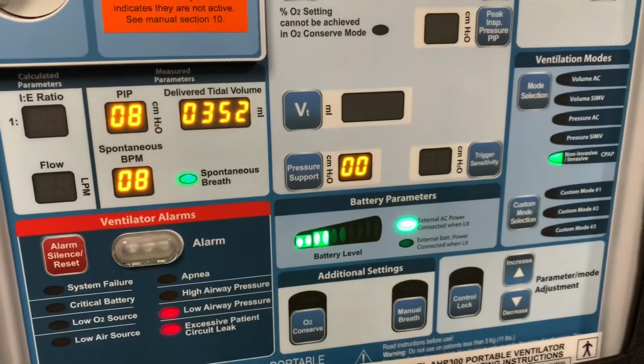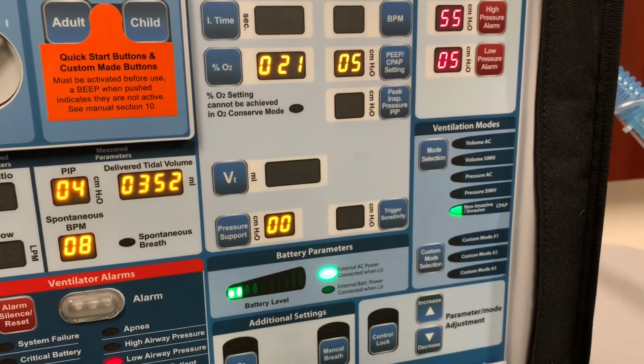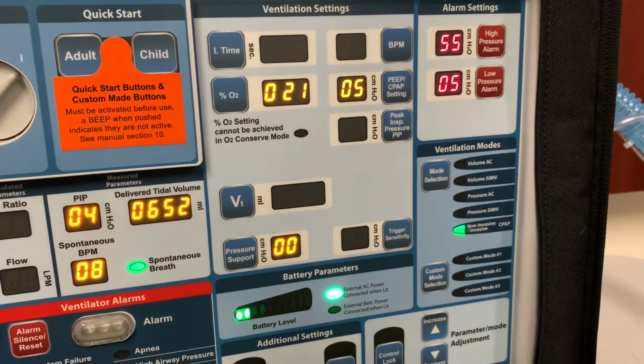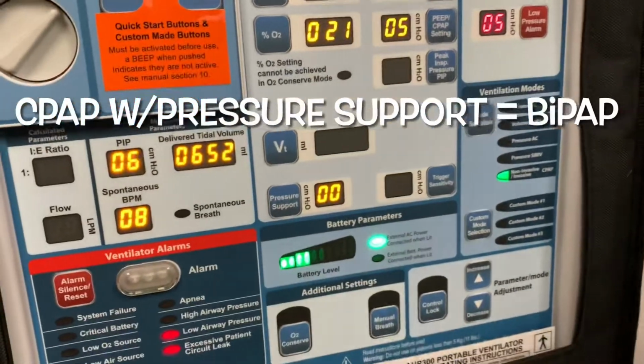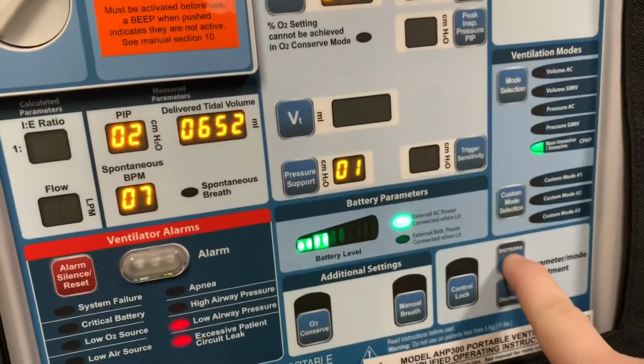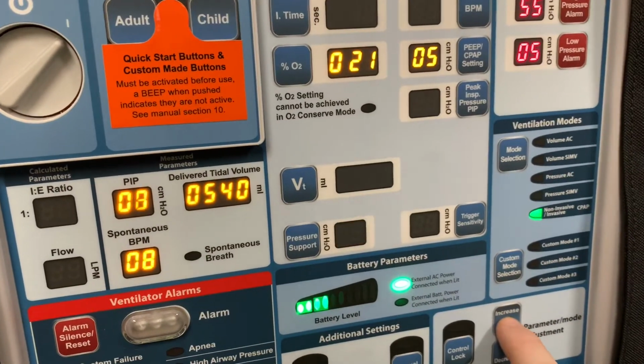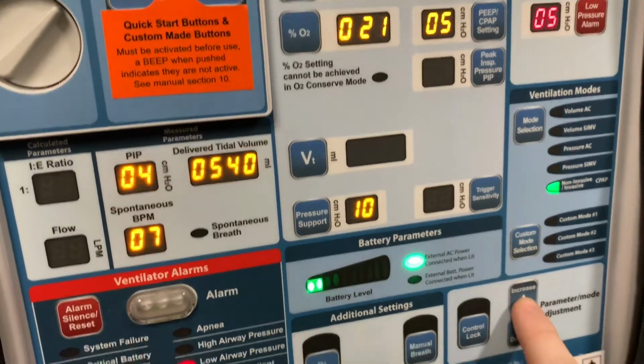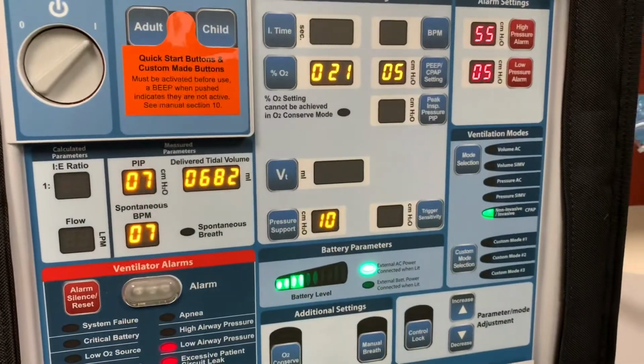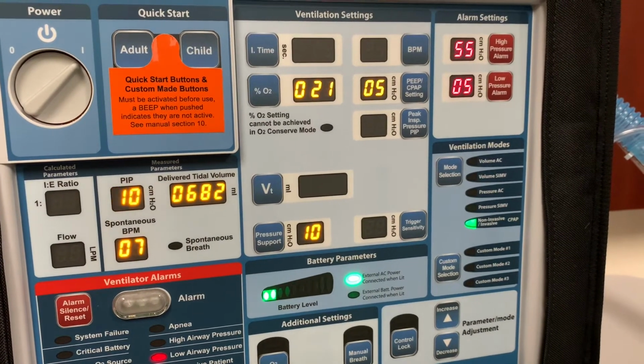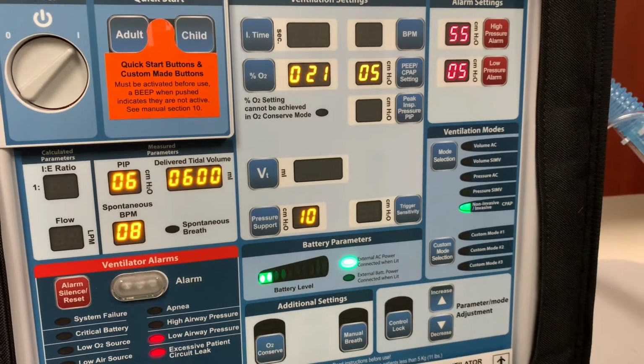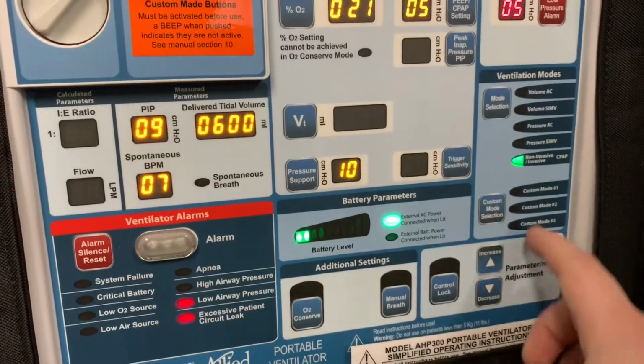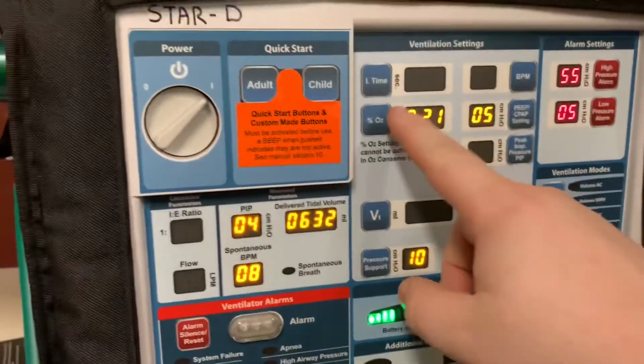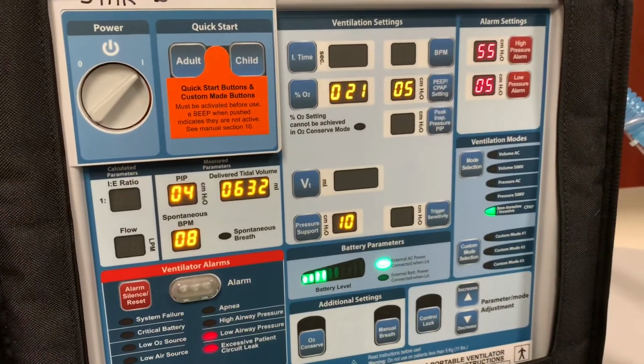Now, my pressure support is currently at 0, which means that I'm just using CPAP by itself with no additional pressure support. Now, if I want to add, I need to increase this. And we'll say we'll make that 10. What this means is that it's going to deliver 10 centimeters of water pressure when Zach here inhales. And in between breaths it is going to continue to deliver 5 centimeters constantly or continuous, hence CPAP. You can adjust this at any time, including the oxygen percentage, so long that you are connected to an oxygen tank of some type.